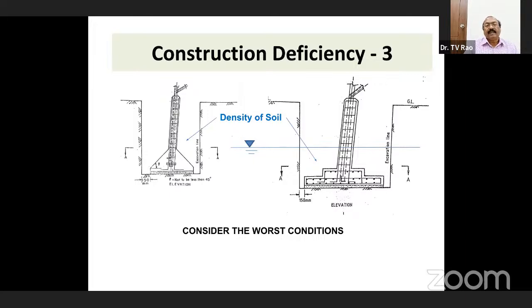So simply, when there is an uplift of 1000 kilonewtons, we designed considering 24 kilonewtons concrete weight and 1690 kg per cubic meter soil weight. Both are reduced - 24 kilonewtons becomes 14, and 1690 becomes 690. Almost 40% of the weight is reduced. So when there is an uplift of 1000 kilonewtons, there is a resistance of only about 600 kilonewtons. So automatically the tower may uproot from the base of the soil.